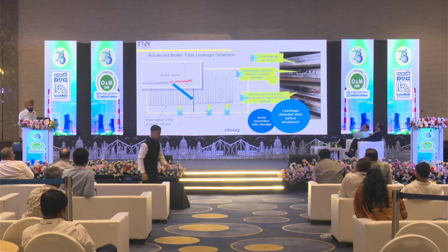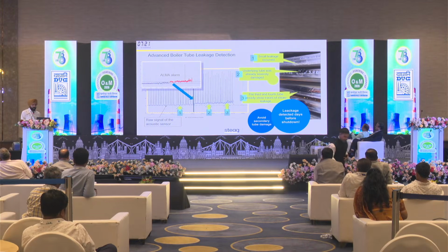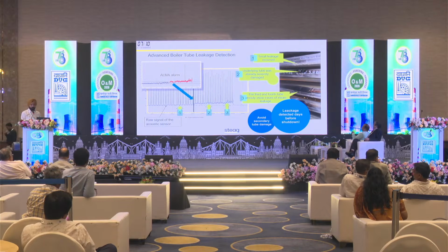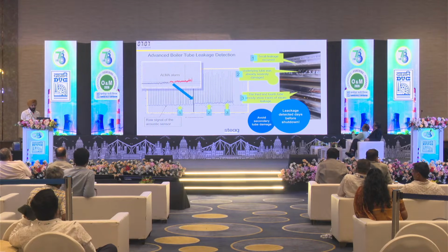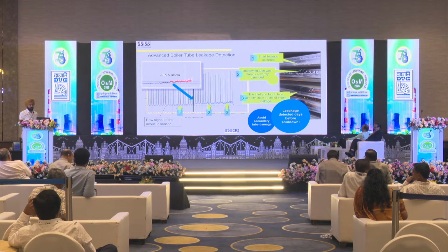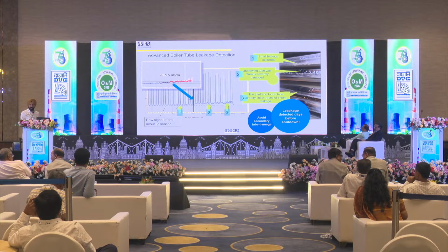So when I talked about the secondary leakages, you can see in this slide that in the background, in the trend, we have the ALMA system installed, and in the background you have the raw signals from the acoustic sensors, the signal being the decibel which is coming. And then there's a processed signal in the front. We have the alarm from the ALMA system. So ALMA has already given the alarm at the stage marked by number 1.